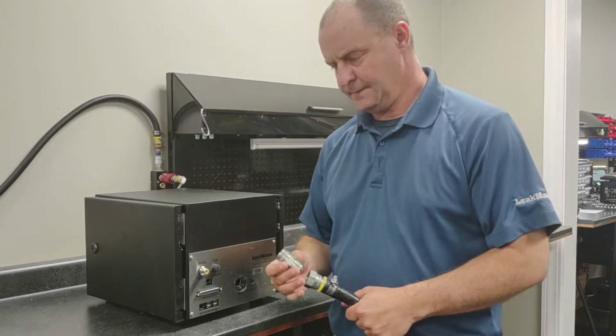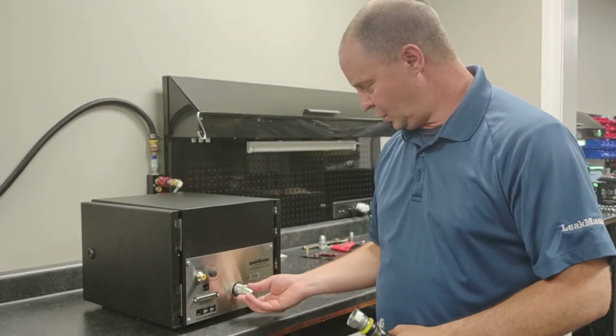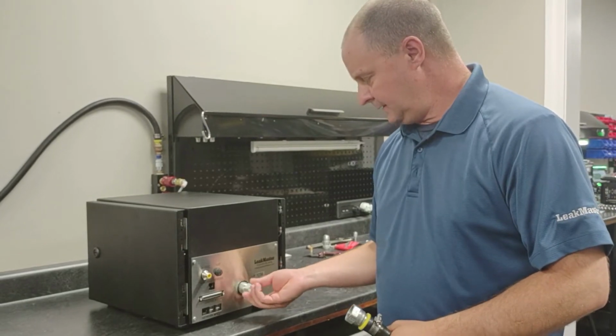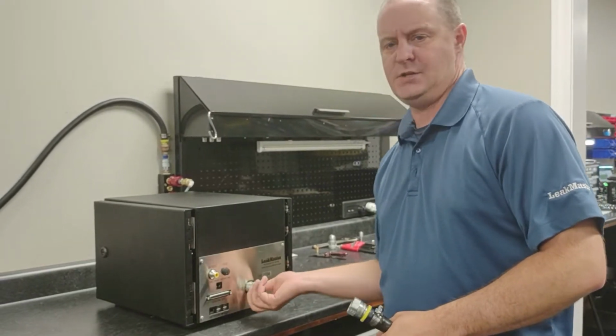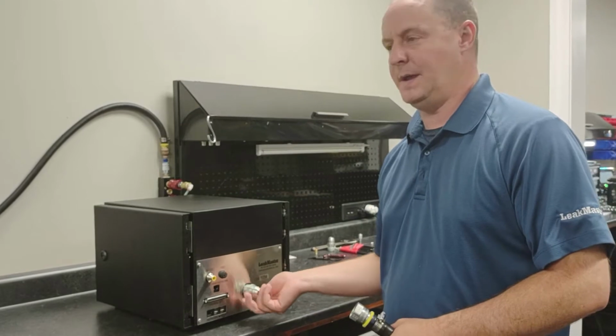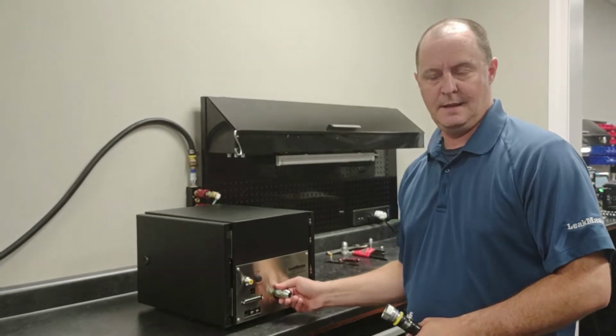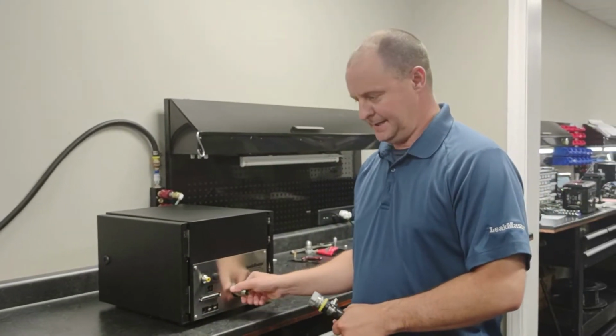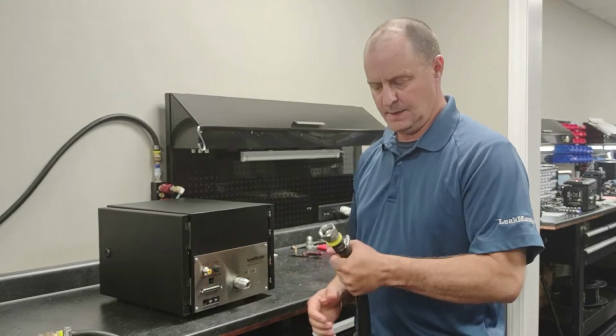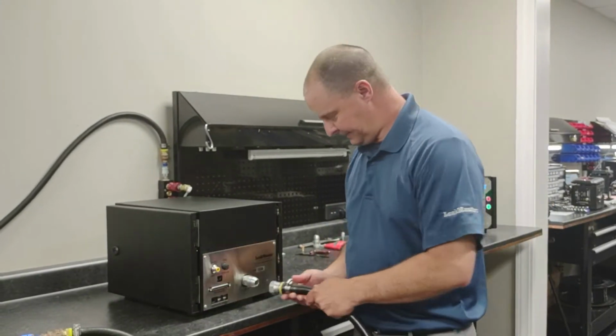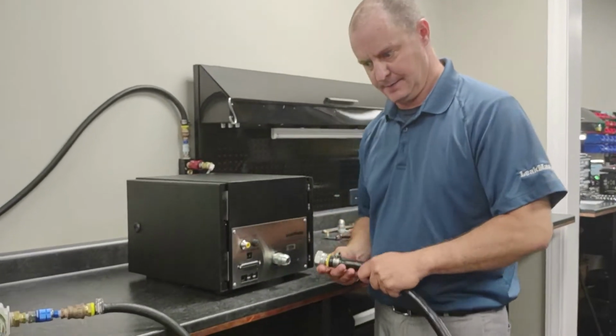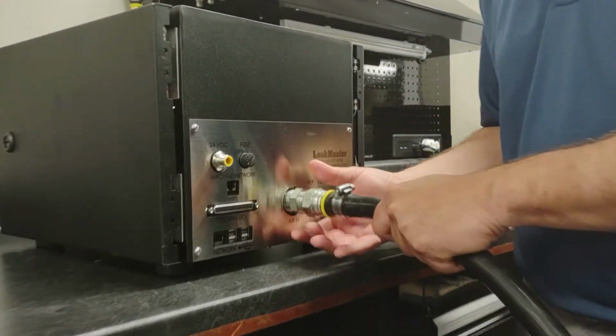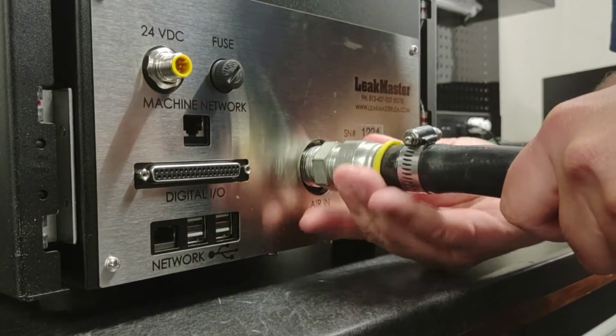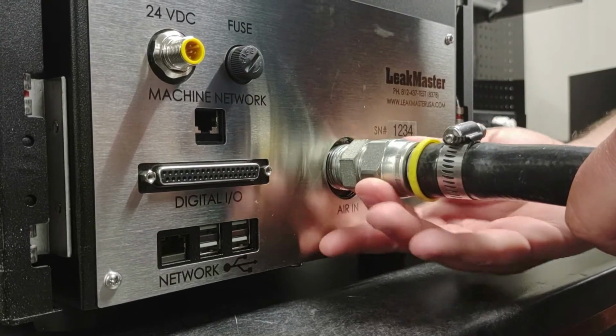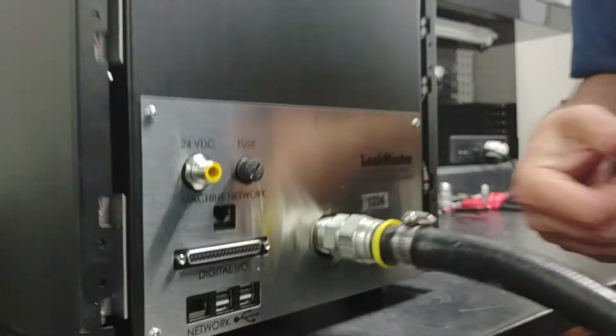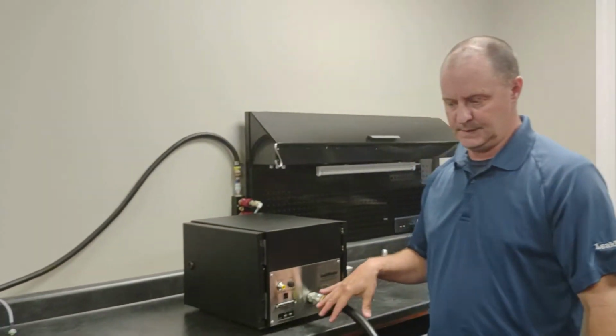I recommend using some sort of fitting that allows you to quickly connect to this. So if you ever had to take this station offline and put a spare in its place, you don't want anything hard plumbed in here where you're having to cut hoses. This is just a flare type fitting. I've already got this mounted on the end of the 3/4 inch line here, and I'm just going to connect to it like this. Now I can easily and quickly disconnect from this unit.